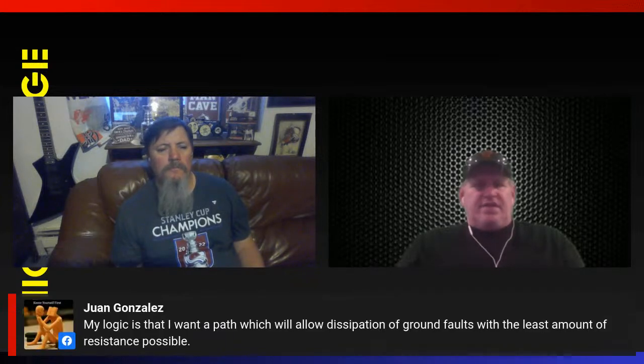Well, let's just look at it this way - there's a lot of determining factors I'd ask before making a decision on that. Maybe they ran over to an AC unit that's 200-something feet away. Now they had to increase the size of the conductors going over there, and based on that size, I would consider that the equipment ground should just match the size of the conductors going over there, since you're going for a longer run.